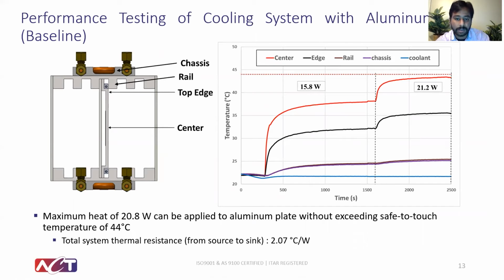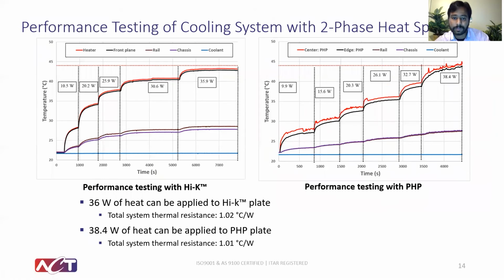the heat spreader. The center temperature is basically closer to the source, and the coolant is the sink temperature. In the baseline case, without exceeding the maximum safe to touch temperature of 44 C, we can transport up to 21 watts of heat. The overall system thermal resistance was a little over 2 degrees C per watt in this case.